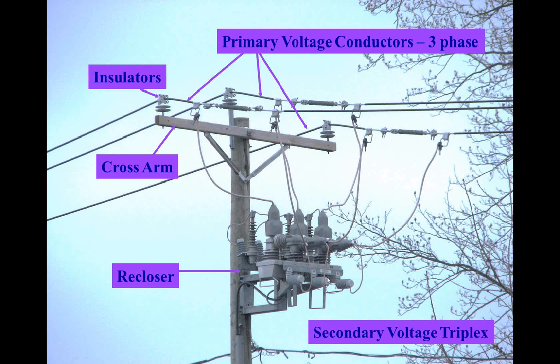So a little farther down the pole, we've got a device right here called a recloser. You guys need to understand what a recloser does. If I had a tree that fell down the street and it landed up against one of these phases of primary, could that tree conduct electricity from that phase through the tree down to the ground? Absolutely. That tree is full of sap. It's full of water. It's going to conduct a lot of electricity. And that's called a phase-to-ground fault.